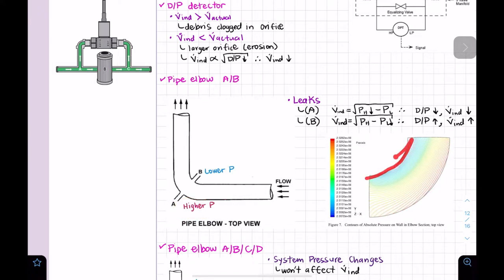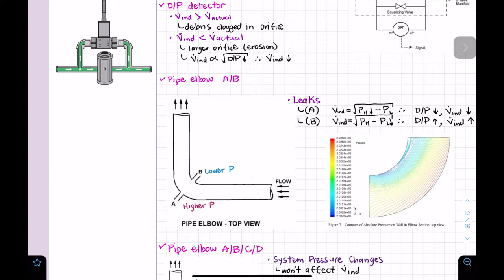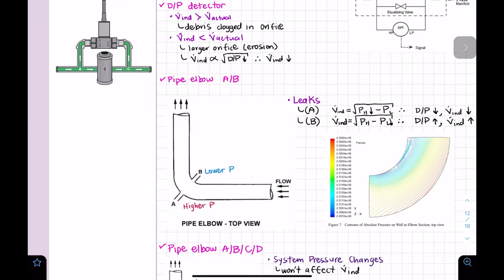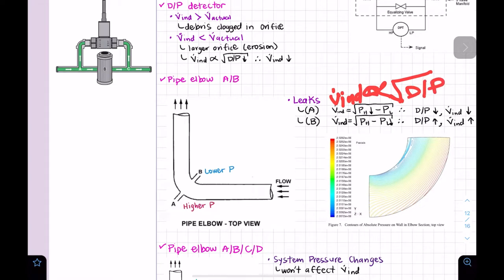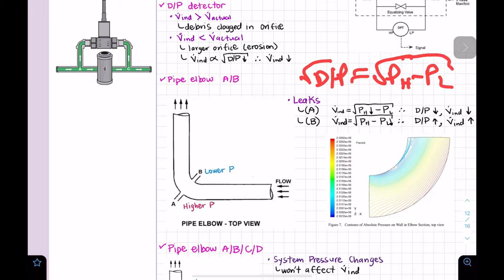CFD simulations also show that velocity is higher on the inner side and lower on the outer side. What we need to know for GFES is the pressure relationship: pressure at the inner part is lower and pressure at the outer part is higher. We use the same relationship — flow indicated is proportional to the square root of differential pressure, which equals the square root of pressure-high minus pressure-low.